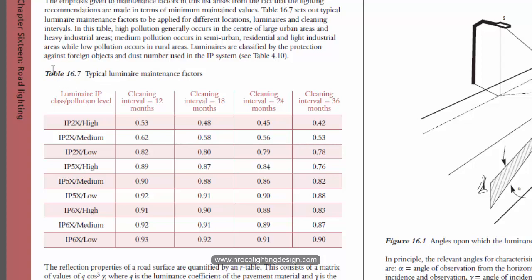So there's a table here, this is the typical luminaire maintenance factor and it depends on how dirty the location is and how protected your luminaire. For example in column one it says the luminaire IP classification and the pollution level.